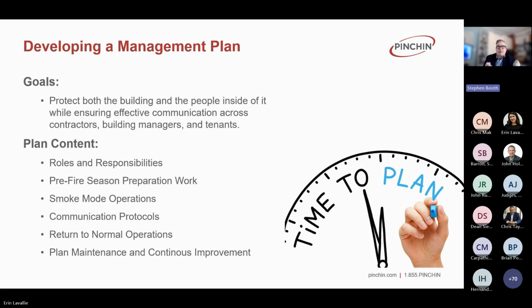Understand how you're going to operate the building differently during a fire versus normal conditions, such as how to control your economizers so they're not automatically engaging and bringing in fresh air for free cooling during a wildfire event, which would be really detrimental to air quality in the building.